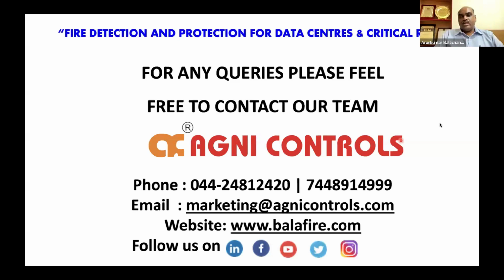Yes, the ember detector is widely used in coal conveyor applications, where it is mounted on top of the conveyor belt, facing the width of the conveyor belt. And it is a moving ember detection. So what we do is we fix it on top of the coal conveyor belt and constantly monitor the material that is moving on the conveyor belt for any smoldering fire.